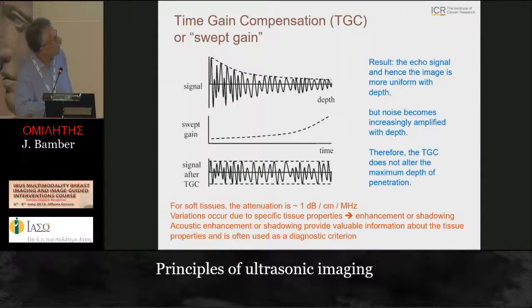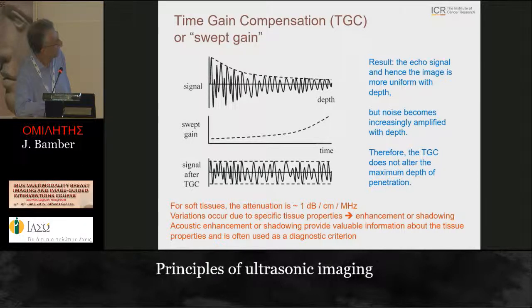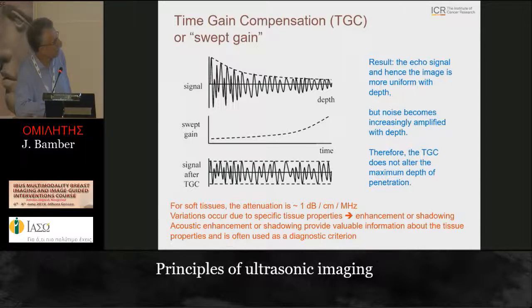Swept gain - also called time gain compensation - renders the decreasing signal with depth into a flat signal. However, it also amplifies noise more at depth. The signal-to-noise ratio is not improved: both signal and noise increase equally. If you go to a depth where there's no signal, it's all noise, and you can demonstrate that on the scanner.